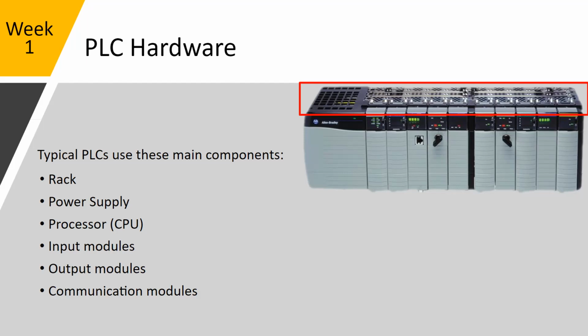Those processors for this family can be in any configuration in any one of the slots. So if you've done some work with some other processors and this looks funny, that's because for the SLC 500 and the SLC 5s and the Siemens and the Schneiders, all of them, the processor typically has to live only in the first slot. That's not the case for 5000.